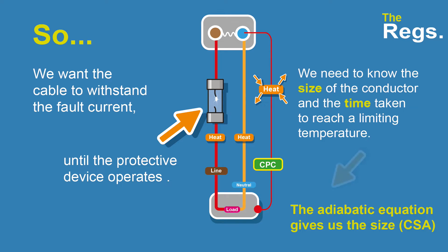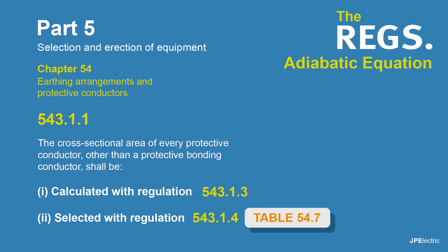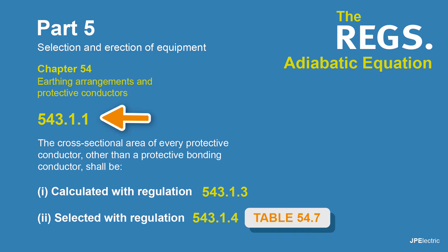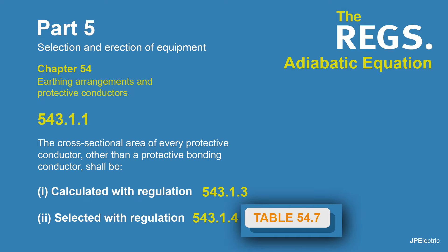The adiabatic equation is for your protective conductors, and it's generally for faults under 5 seconds. It's mentioned in Part 5 of BS7671, Selection and Erection of Equipment — Chapter 54, Earthing Arrangements and Protective Conductors. The regulation number is 543.1.1: the cross-sectional area of every protective conductor, other than a protective bonding conductor, shall be calculated or selected. The adiabatic equation is the calculated method, or there's also a table that we can look at, which I'll mention further on in the video.